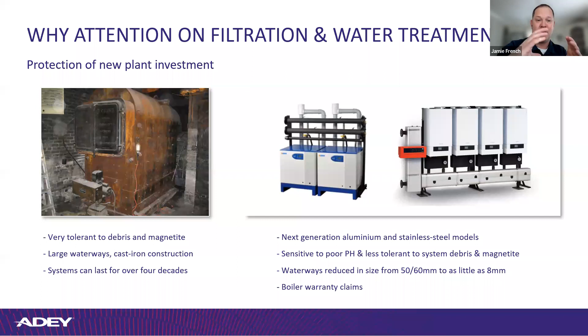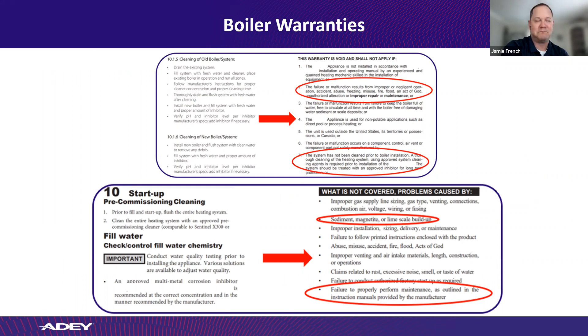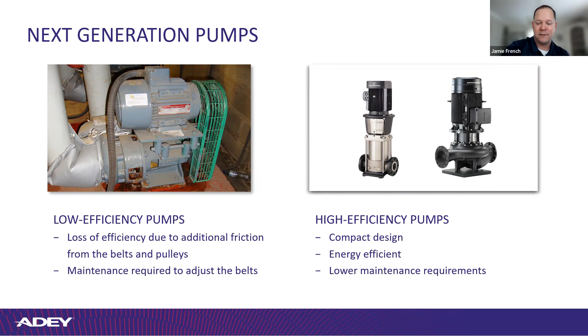So boiler manufacturers are starting to make note of this and pointing out in their warranties that water quality matters. It's important. And they're starting to bring those back into their CSI labs, cutting them open. And if they find magnetite, they're starting to reject warranties. So it's important to make sure you're dealing with it. And then we go to the next generation pumps, the one on the left. I still haven't seen one like that, but I know they're out there with belts and just poor efficiencies. Now we go to the ones on the right, high efficiency, again, smaller. A lot of these use magnets in them in order to run efficiently. If you think about ECM circulators, they use neodymium magnets in there too. So if you're not pulling it out with a specific device, chances are your pump is going to start pulling it out for you, and that's an expensive replacement.